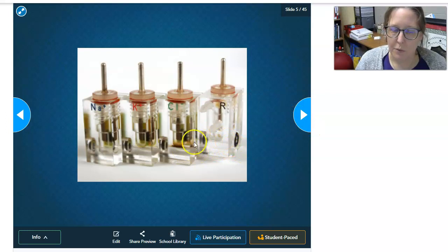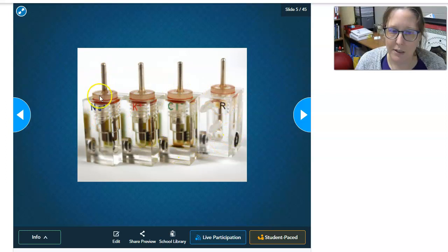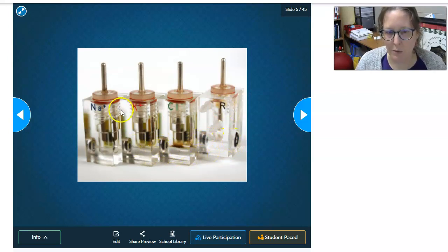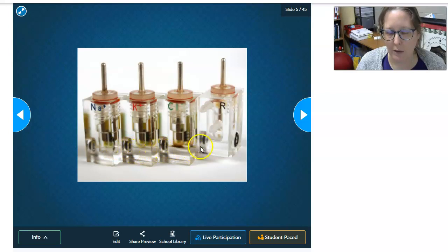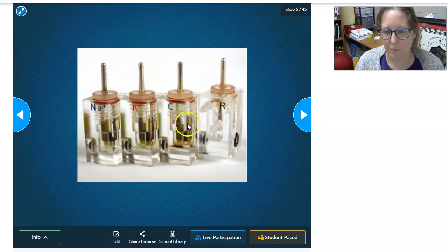Here is an example of the older version of the electrode — a bit bulkier, though they've been miniaturized. The sodium electrode has a specific membrane, and so does the potassium one and the chloride one, plus a reference electrode. The sample goes through this area — through the sodium electrode, then potassium, then chloride, then the reference — giving readings of sodium, potassium, and chloride concentration in each.